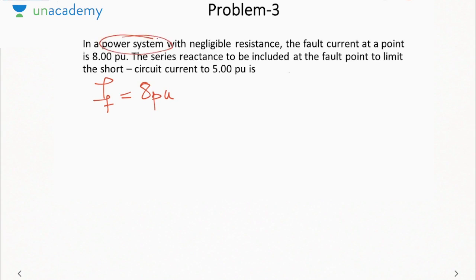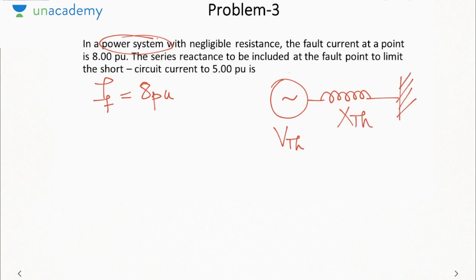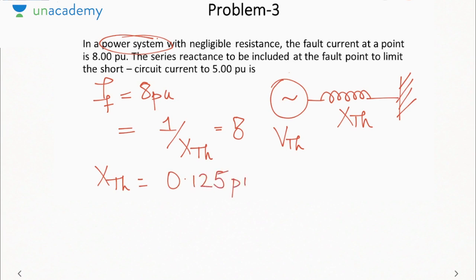Whenever we are talking about power system, one thing that you must remember is we will replace the power system by a Thevenin equivalent, that is V Thevenin in series with X Thevenin. Now it is connected to a bus bar. So what happens is that fault current IF is 8 pu. So IF is equal to 1 by X Thevenin, which is equal to 8 pu. So it implies X Thevenin is equal to 1 by 8, which is equal to 0.125 pu.